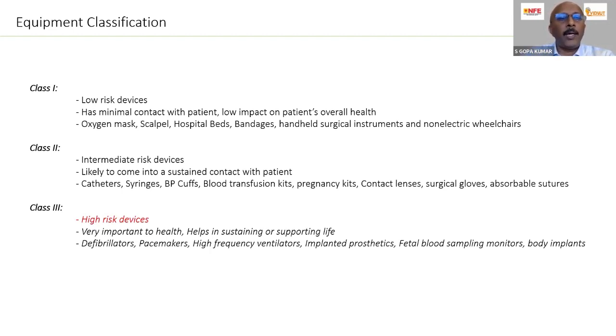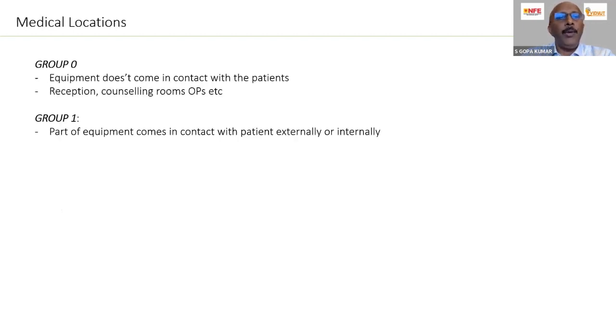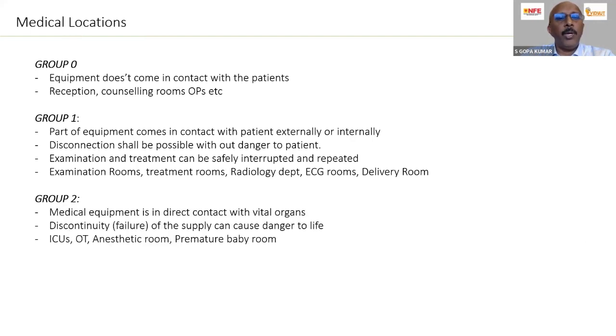So like other electrical applications, here also for medical locations, class 1, class 2 and class 3 devices are used. The use of these devices is classified into three groups: group 0, group 1, and group 2 medical locations. Group 0 is a medical location in a hospital where the equipment doesn't come in contact with the patient. That is the normal area. Whereas group 1 is an area where part of the equipment comes in contact with the patient externally or internally, mostly on the surface of the body.